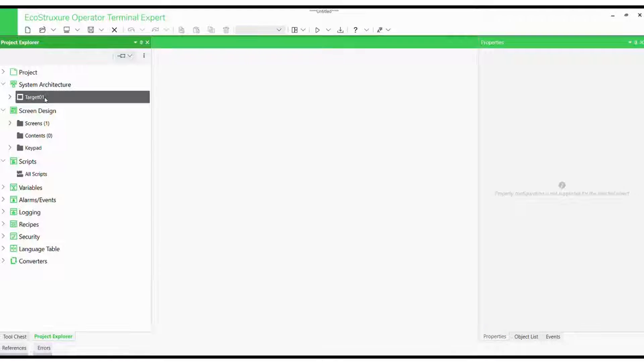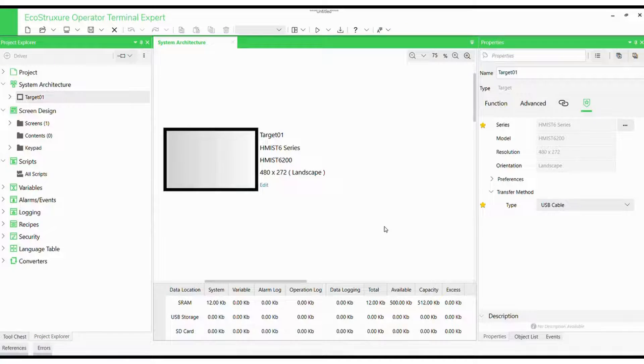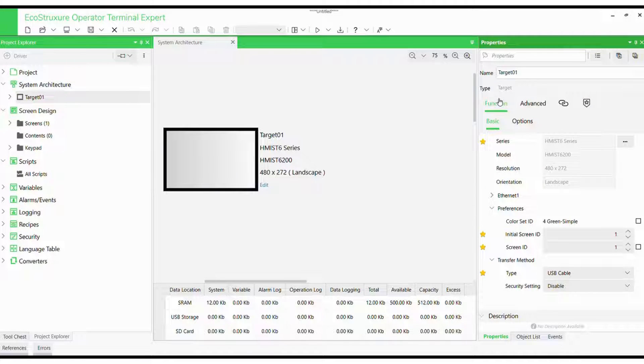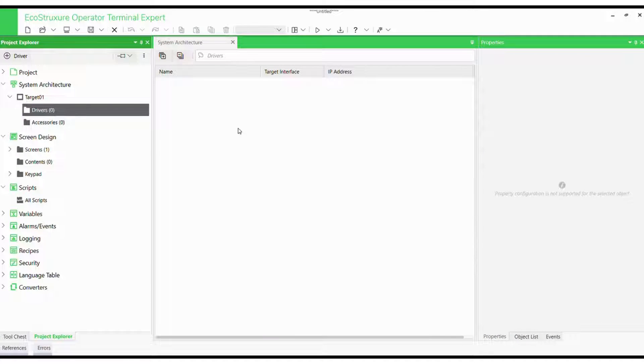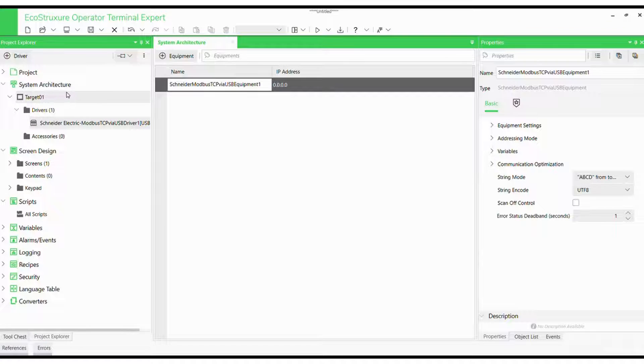Alright, software fired up. Create a new project, click on System Architecture, Target01 in the Project Explorer. We will define the target device as the Harmony ST6, specifically the HMIST6200 model with a 480x272 resolution. In the Function tab, click on Transfer Type as USB Cable. Now click on System Architecture, Drivers, and select the USB driver under Schneider Modbus.